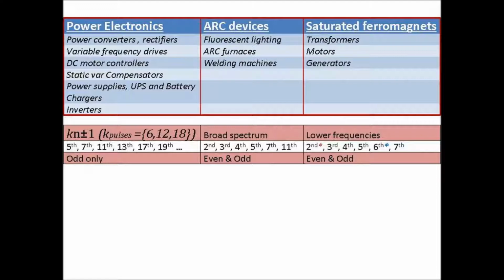And then transformers, motors and generators. I have an asterisk beside the 2nd for transformers, purely because it only happens when they are energizing, and after a second or two that clears. But it does exist for a few seconds, and if you've got sensitive load, there can be a problem. 3rd, 4th, 5th, 6th, and 7th are basically the lower frequencies to do with transformers, motors, and generators. The 6th is actually an artificial harmonic that comes about because the 5th and the 7th give a torsion on the system, and it ends up inducing the 6th harmonic on a shaft or a bearing. So that's the harmonic sources.